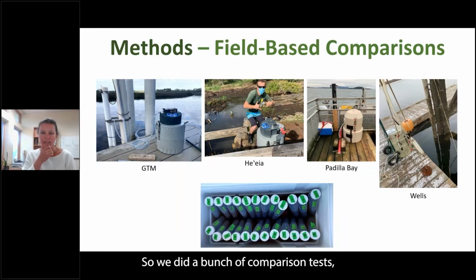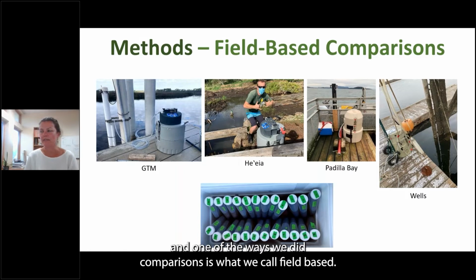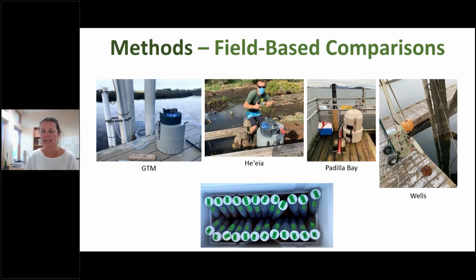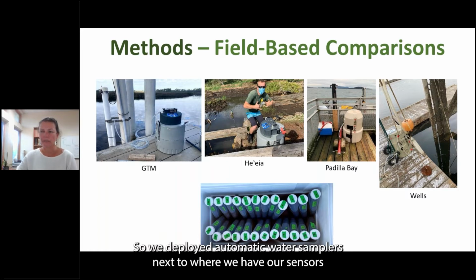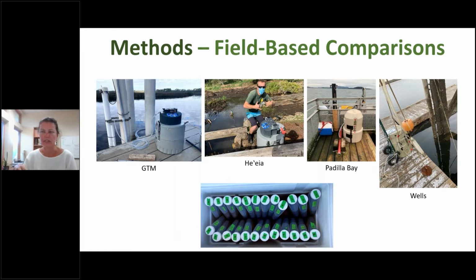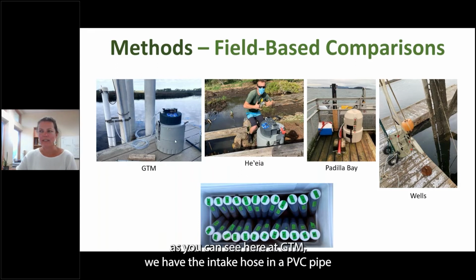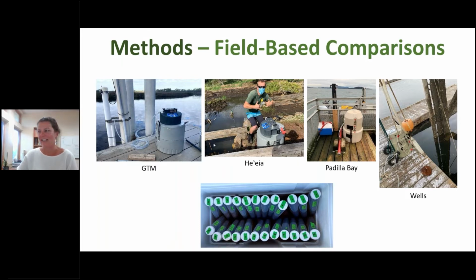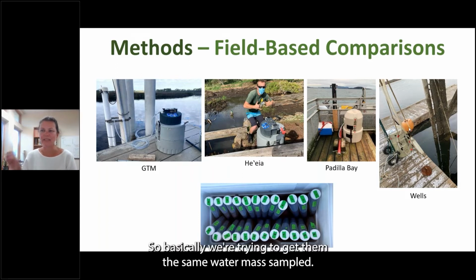So we did a bunch of comparison tests, and one of the ways we did comparisons is what we call field-based. So we deployed automatic water samplers next to where we have our sensors installed for the system-wide monitoring program. We did this in a number of different ways depending on the site. As you can see here at GTM, we have the intake hose in a PVC pipe strapped to the PVC pipe where our data sonde is. Over at Wells in Maine, they had this float system set up. But basically, we're trying to get the same water mass sampled, but it's hard to do perfectly in the field.